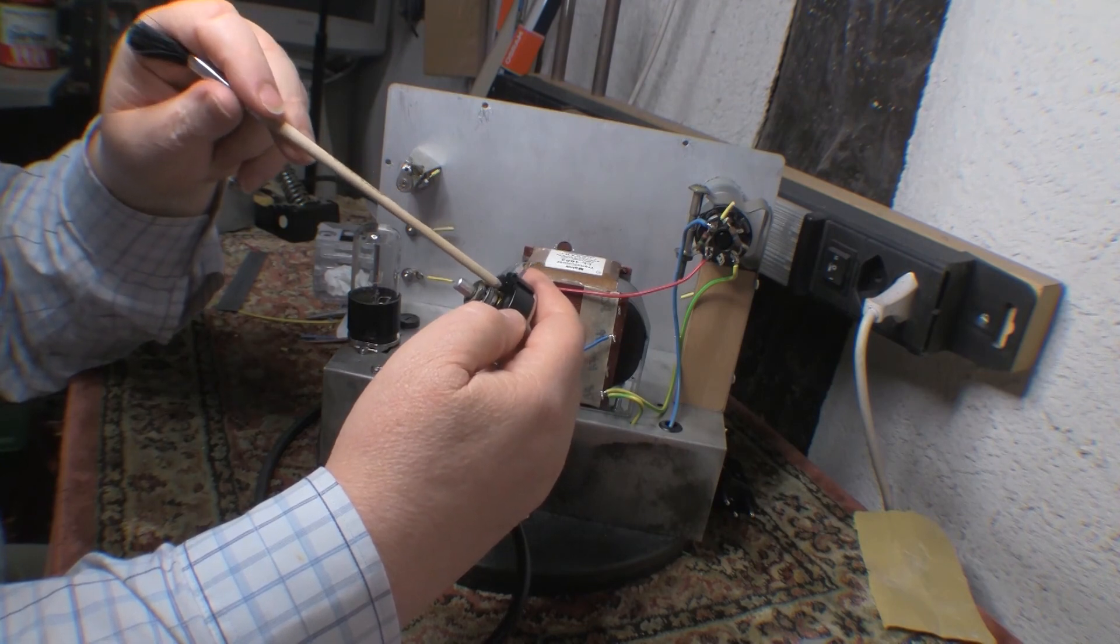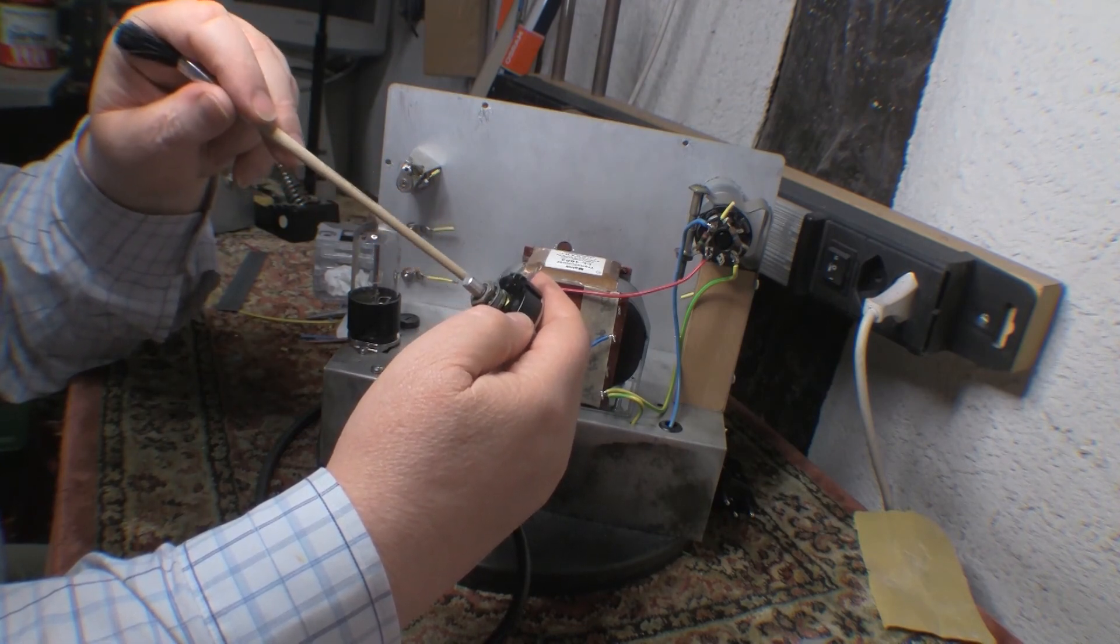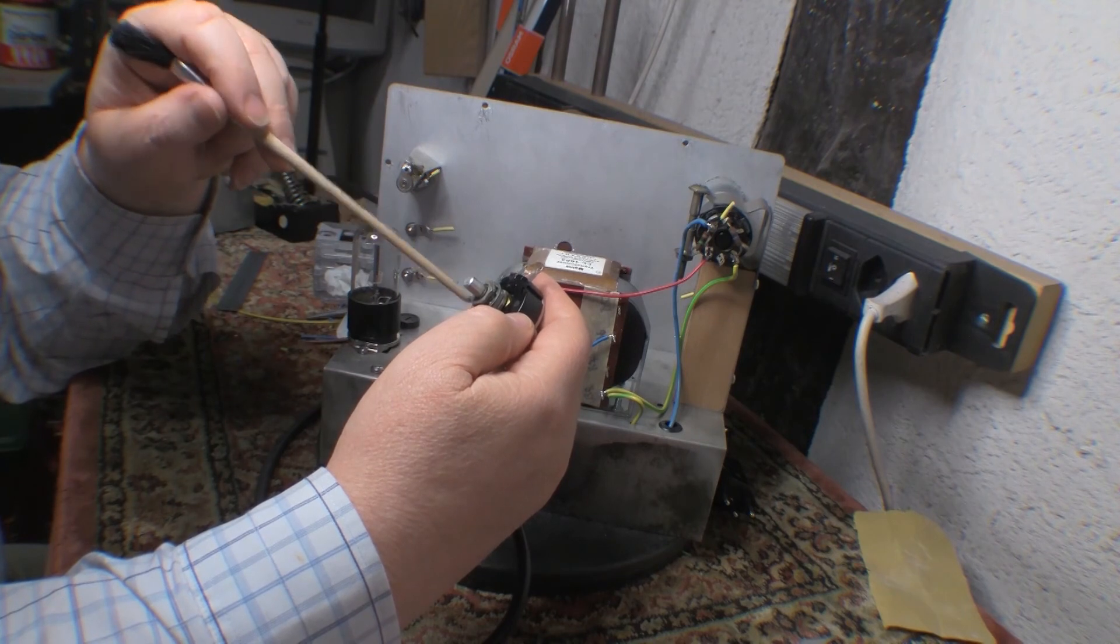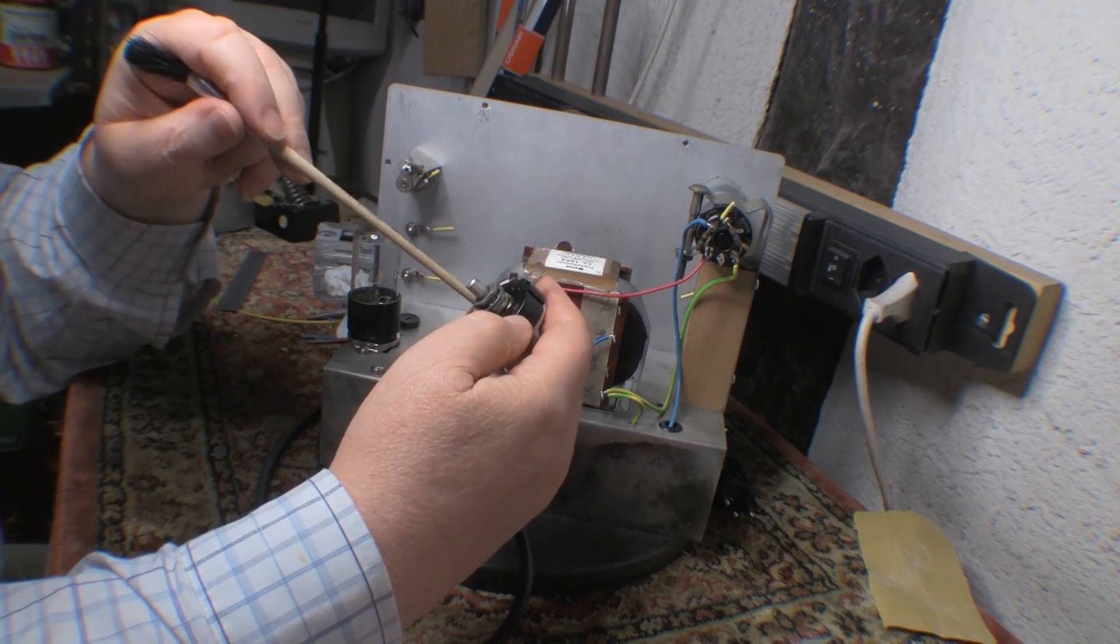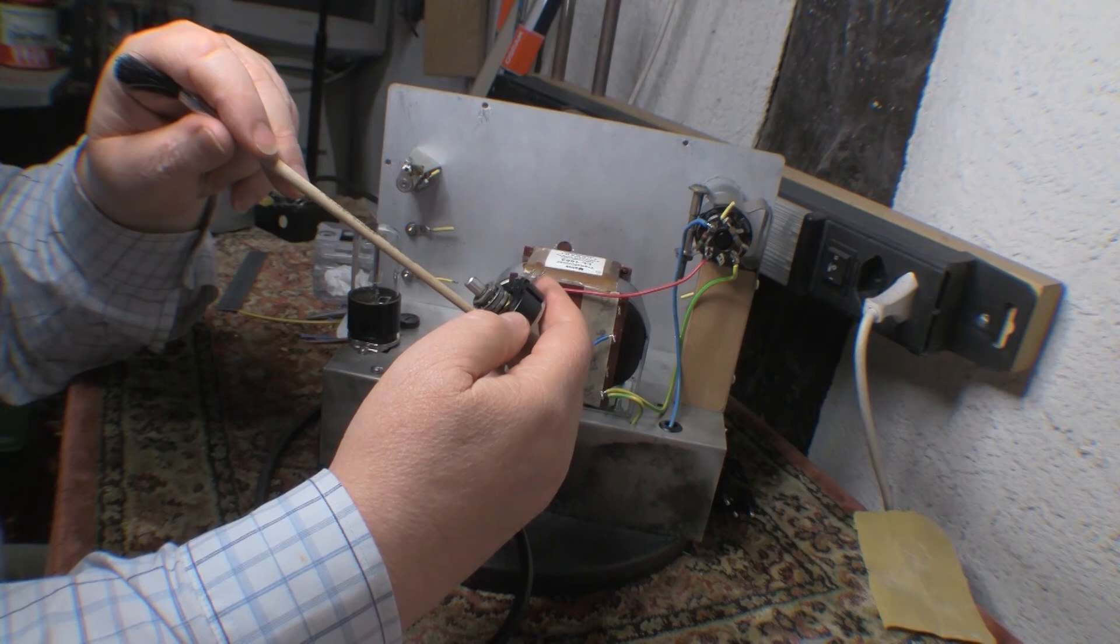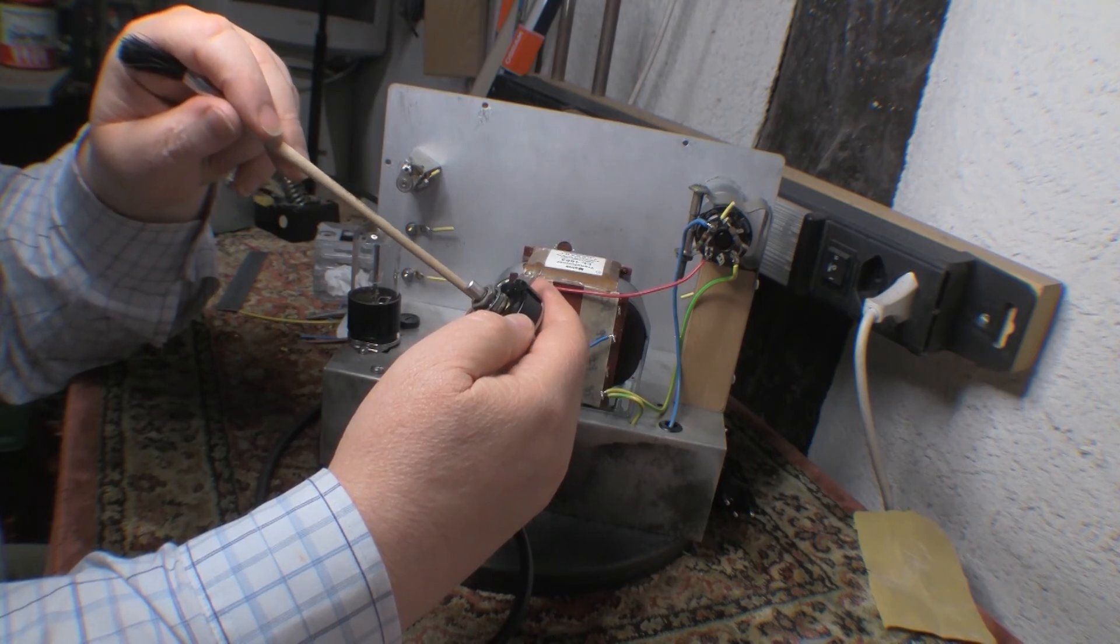So the resistance wire has sort of tended to bunch up in places, and then there's gaps in other places. And so as the wiper comes around, it encounters these little areas along the travel where it's not actually touching any of the wire.